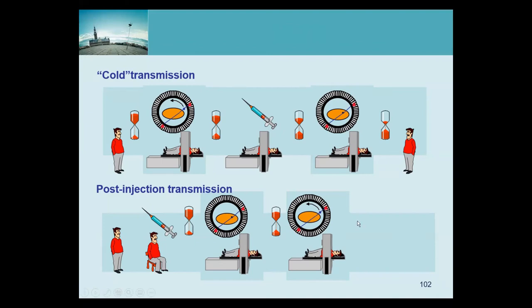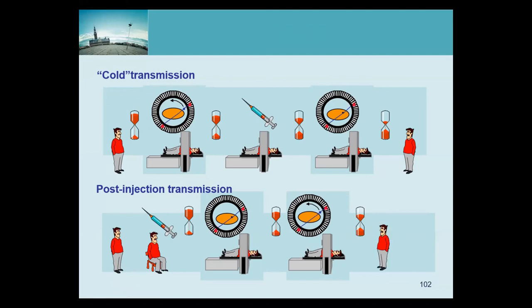You can do the same thing as in SPECT imaging: the sources are rotating, but the scanner knows where they are, so it can tell us at every time in the list-mode file exactly where the source is. Then we know that only LORs passing through one of the sources can have anything to do with transmission. If they're not going through that source, they are emission, scattered, or something else. That way, the contribution from non-transmission measurements could be suppressed dramatically.